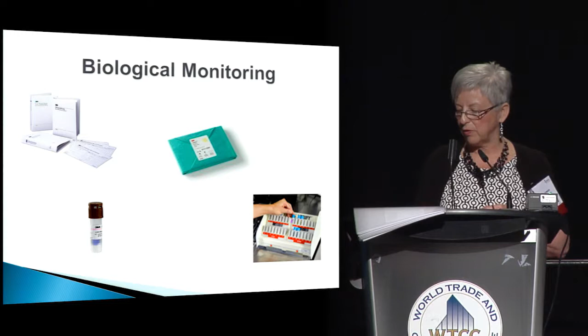With your BI, the BI PCDs come with a control, a package of controls. They'll come in a lot and they'll have a package of controls. These controls you put in the incubator without processing, and the chemical or the enzyme in there will change to a positive. And then you have the one that was in the sterilizer, the test that you're measuring it against. So hopefully the one that went through the sterilizer process will pass, and the control will fail. And it just shows you the difference in the media. So the control has live microorganisms, and the one that went through the sterilizer wouldn't.